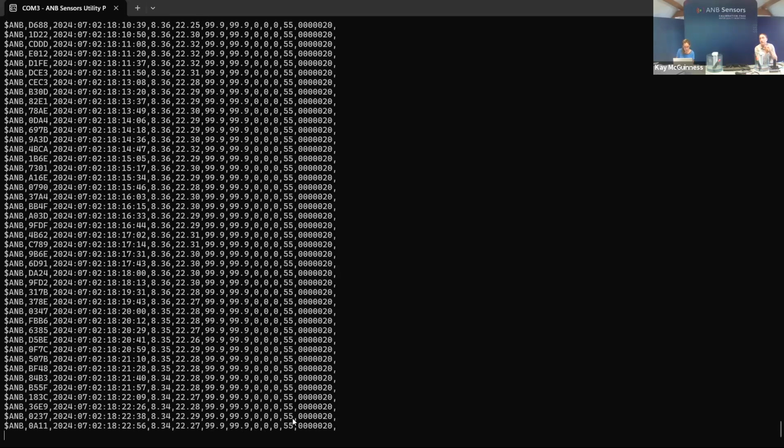Perfect. So we can now maybe have a closer look at the health number and the sensor diagnostic number. Yes, let's do that. So this really sets us apart from the glass electrode, doesn't it? Getting feedback from the sensor on how it's performing. We've had some horror stories on the glass electrode where lots of data was coming back and it all seemed fine, but when they went there, it was actually broken. Exactly. Everything appeared well, but it wasn't actually working properly.